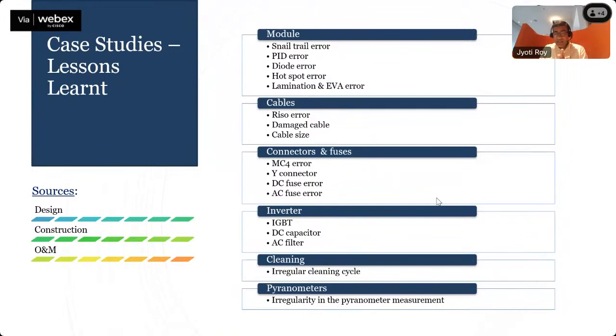That's one example. Another is the connector issue—particularly common in India, where a small 4 square mm cable connects via a Y connector to a 6 square mm cable coming out. That Y connector is one of the weakest links.